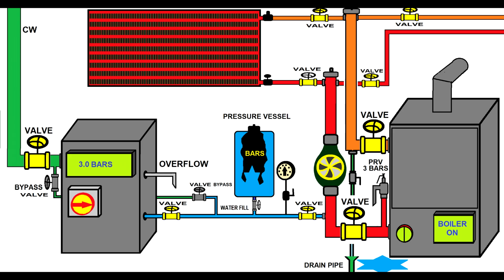In this case, the boiler is running, and the heating agent is hot, but as I said, the extra volume has already been eliminated by the PRV. The problem, as I said just before, is when the system goes off, because the heating agent pressure will drop a lot because the volume will shrink, and the pressurization unit will try to compensate, and by compensating, the pressure will bring back the volume which was lost when the system was running.